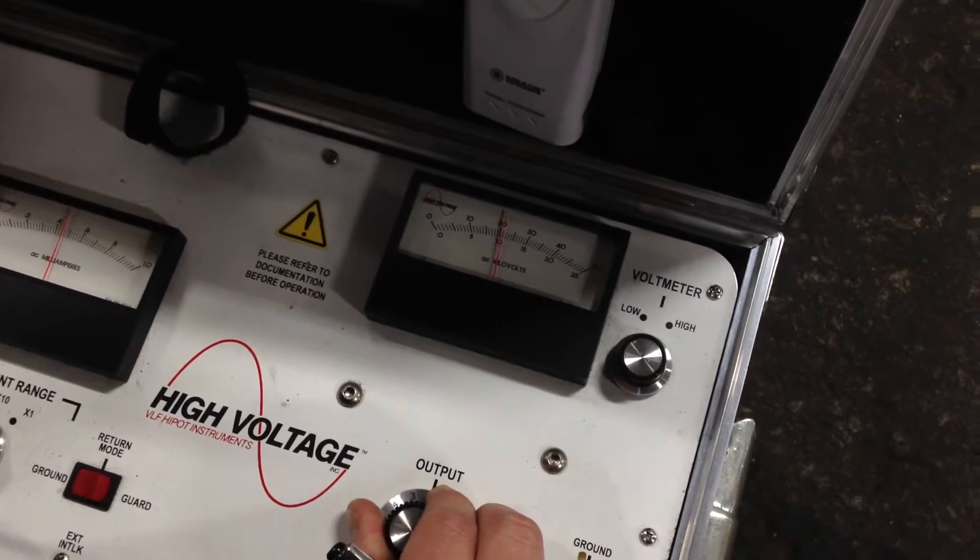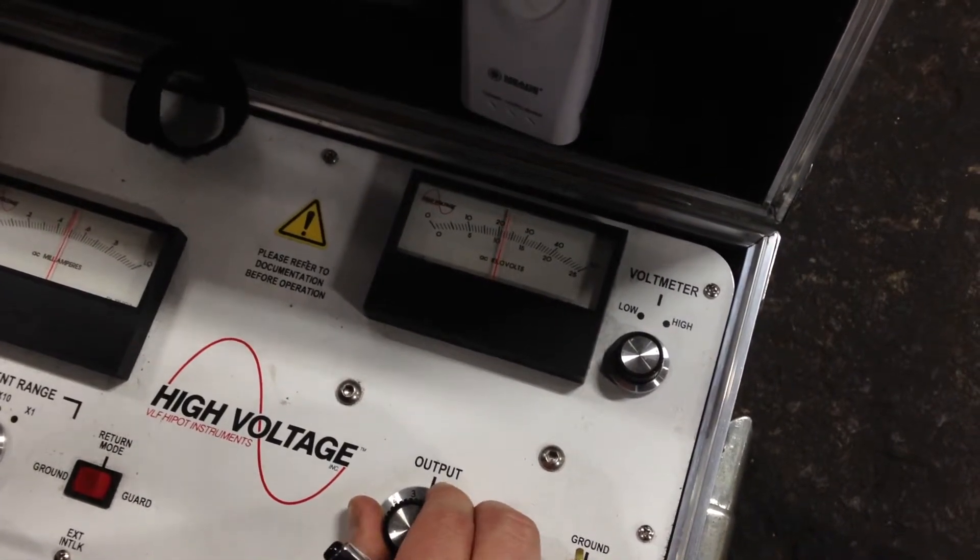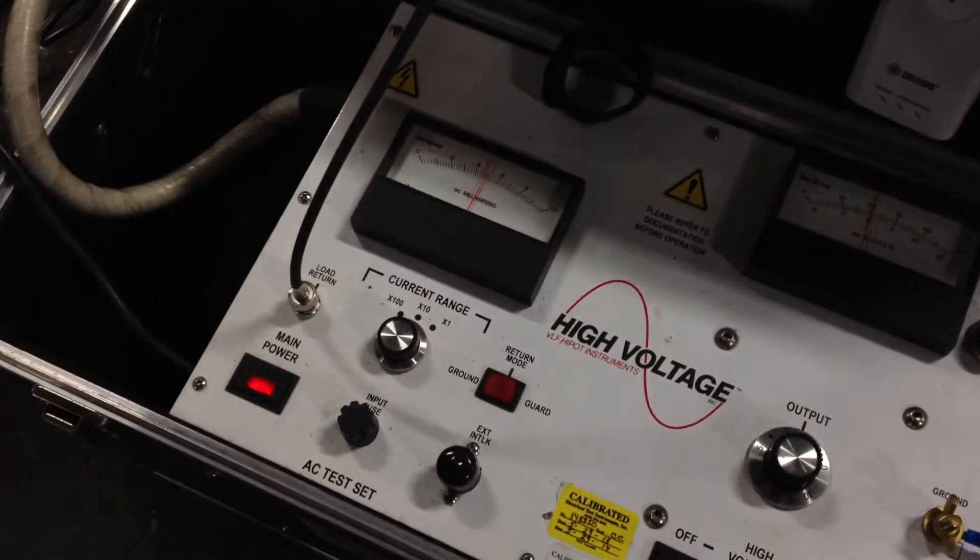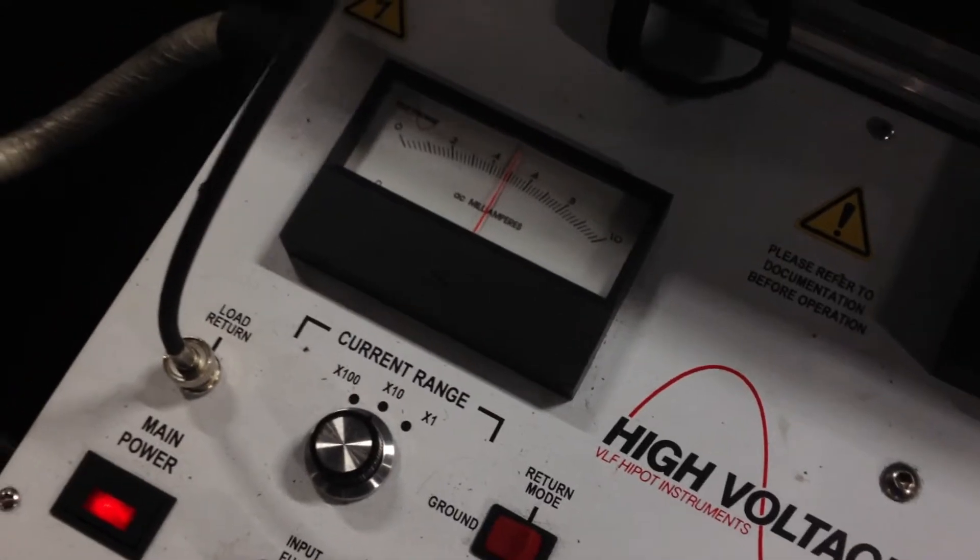We're up to 11.4 kV, right about there, and we should be getting right around 5.0 for our reading, which is within tolerance, which is perfect.